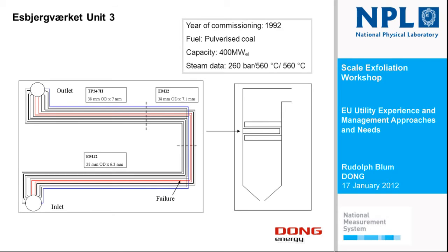And thanks to a proper arrangement and good luck, we were able to detect all tubes which have been affected and replace them if they were overheated, and then later have a troubleless service. So this is what happened in this case.